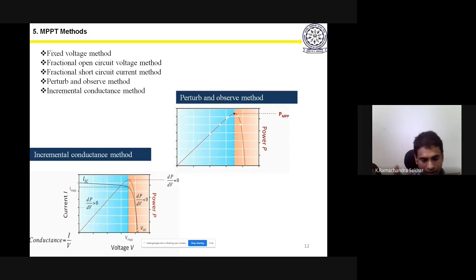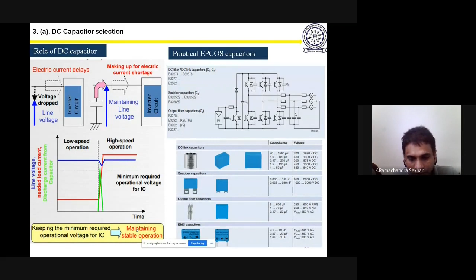Now I want to explain how to size the capacitor. The reason for so much emphasis on the capacitor is that it's the most vulnerable device, and it decides the life of your complete inverter, because capacitor life is mostly 5 years, but the inverter switches can last up to 10 years. That's why sizing of the capacitor is more important. How you size the capacitor is crucial when you sell any product, because oversizing will attract a lot of cost, and undersizing will deteriorate the life of your converter.